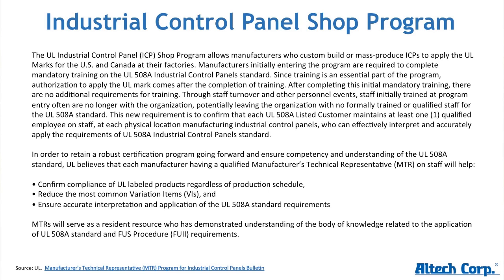You have to go through training. You have to have at least one dedicated technician on staff. He's called a manufacturer's technical representative, and he will assure that all the 508A guidelines in the panels are met. You have to document all the components you're using.